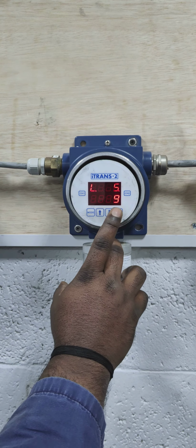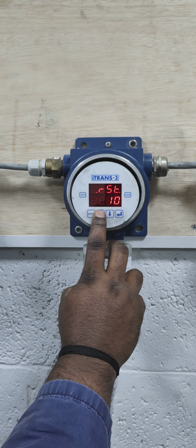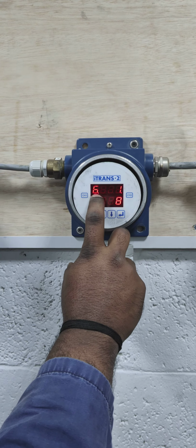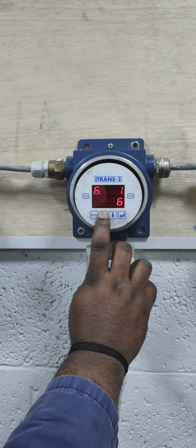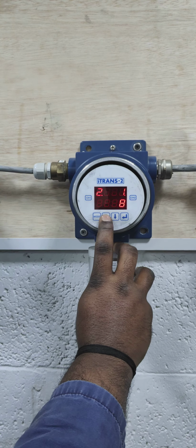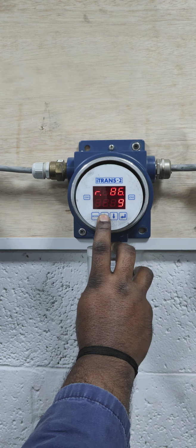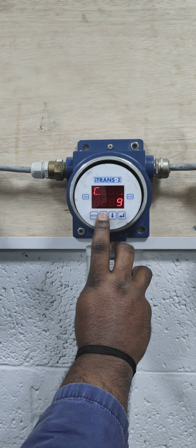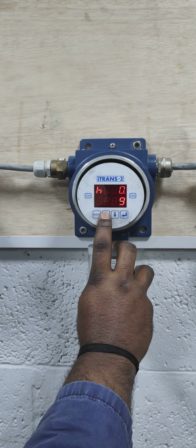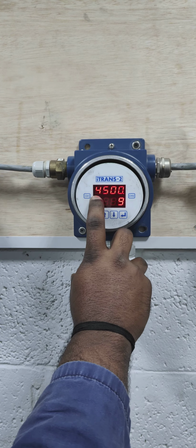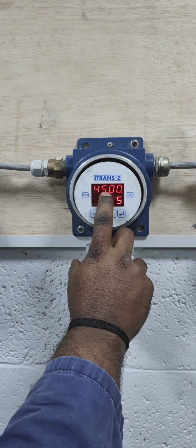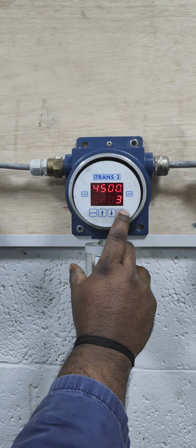So now it is KL, and then we need to select here one by one. These are all the codes, which we have available in the manual. So we need to check what this number is. So this is span calibration mode 0, and for the range it is 4. This code number 4 is the range. So now here it is 500. So I need to change this one to 100.